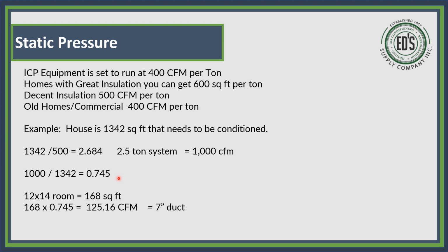Now, some of the super cool slide rules and stuff, they use a 0.80 flat rate. So you can't go wrong because you're talking about minute numbers. So if you want to go 0.80, that's fine. If you want to go accurate, this is the way you do it, and you'll find out exactly what it is. So now let's say we've got a 12 by 14 bedroom. We multiply that together, and that's 168 feet. Then we take our 168 feet, multiply it by our 0.74, and we get 125.16 CFM.